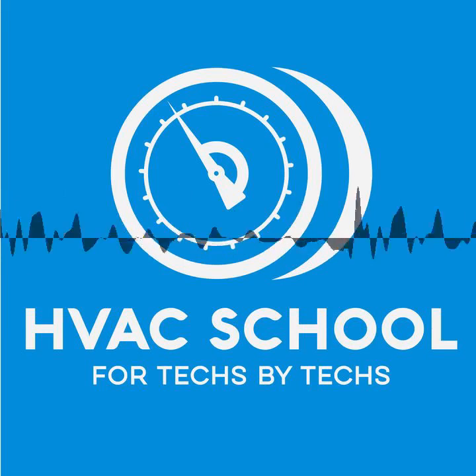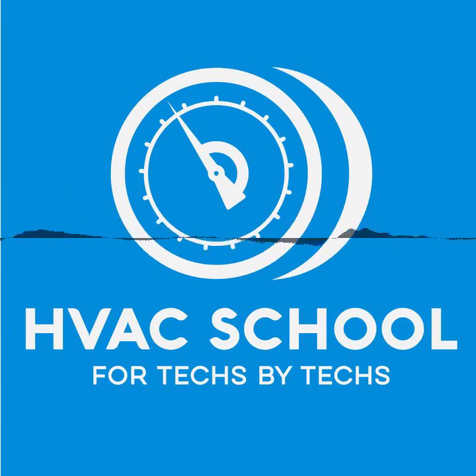You also have to have a variable speed blower that adapts to what that compressor is doing, because otherwise you're not going to have a coil temperature that remains stable. And so in the past, what we've done is we've done just the blower without the compressor. And so we don't have a stable coil temperature in a lot of cases on purpose, because we're trying to drive down the coil temperature in order to remove more moisture.